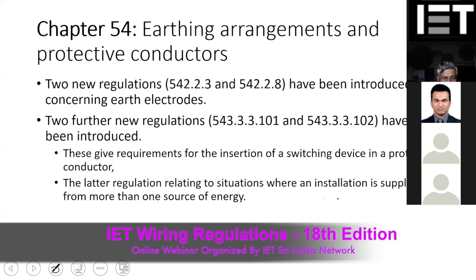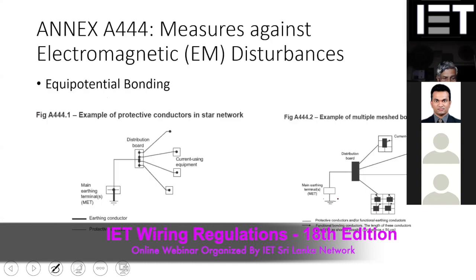Okay, what type of earthing should be there? Those new regulations are added to the standard, so you can refer to them. These are a few of the new requirements added to the standards. And also, as I said, the standard now recognizes that electromagnetic disturbances are very common in most installations because of equipment behavior and equipment patterns. Because of that, equipotential bonding is highly encouraged, and it is given as a mandatory requirement.